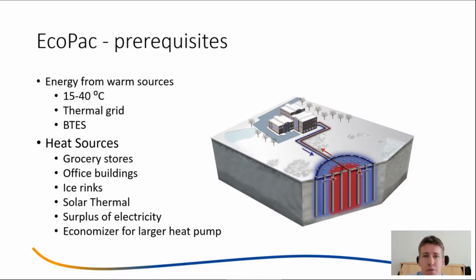What is different on this type of machine from a normal ground source heat pump or an air heat pump is that we're aiming to connect this to something that is a bit warmer than the ground. So we're looking to connect it to something that is around 15 to 40 degrees. That could then be a thermal grid or a thermal energy storage, and most likely a borehole thermal energy storage.